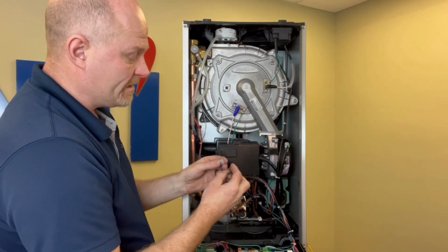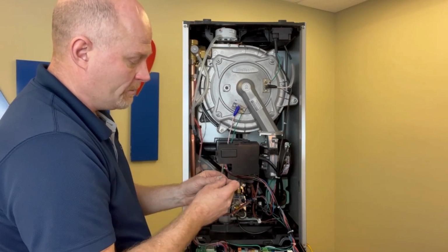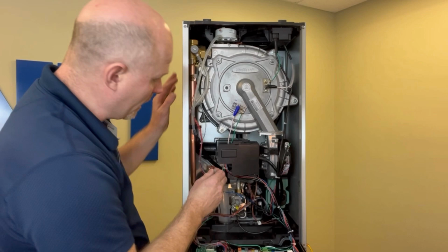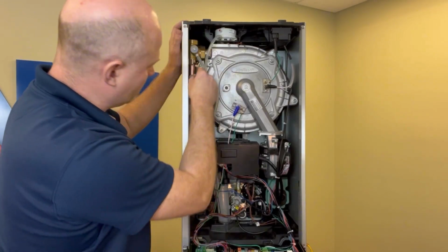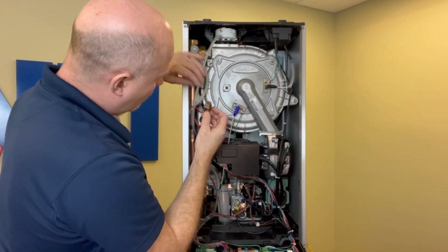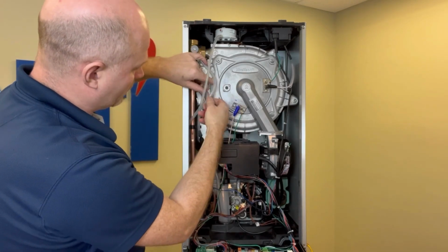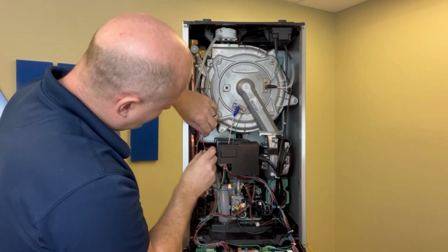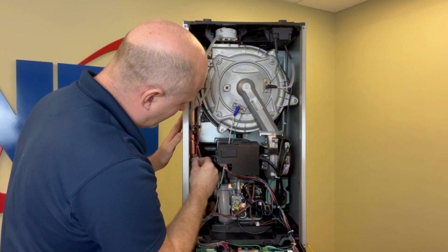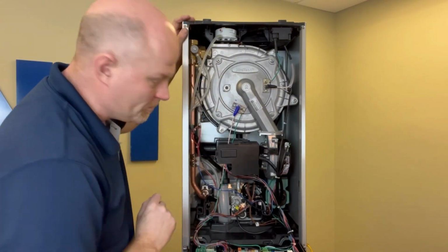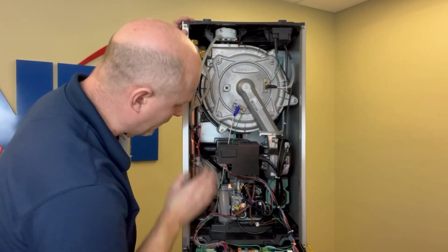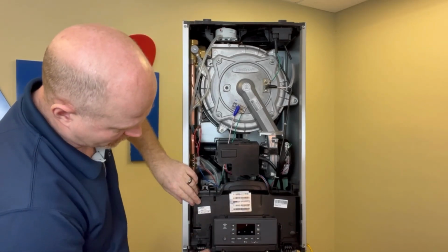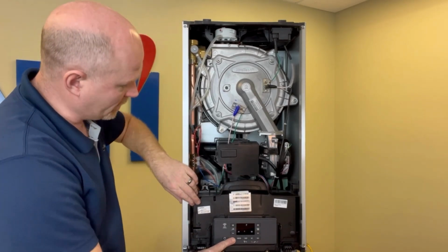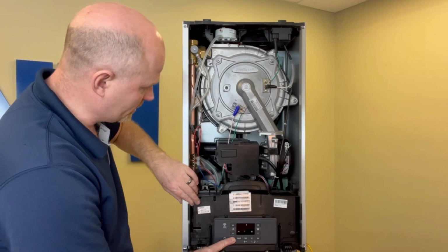Now, a really good test at this point is to verify that both sensors read the same. The way you do this is you simply clip both sensors onto the same section of pipe in the boiler. So we're going to put both of those side by side. Give them a second to normalize. Then we're going to go into our menu by pressing and holding. After 5 seconds, we should see info.